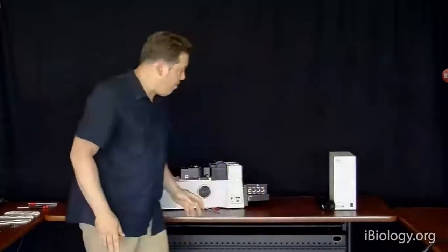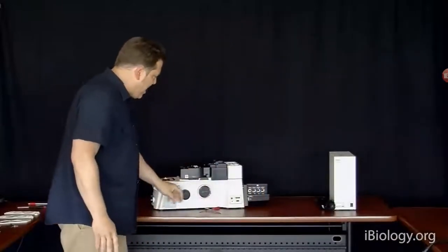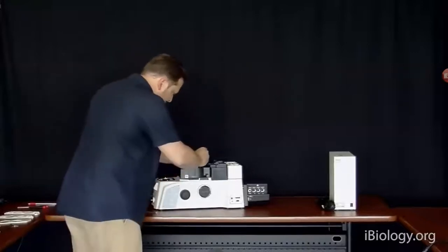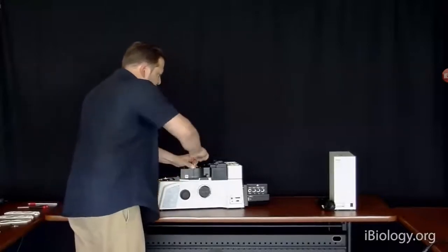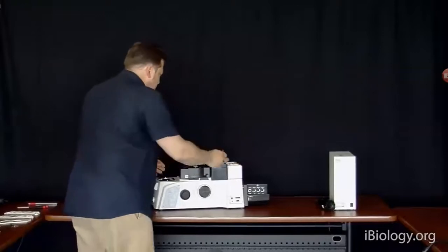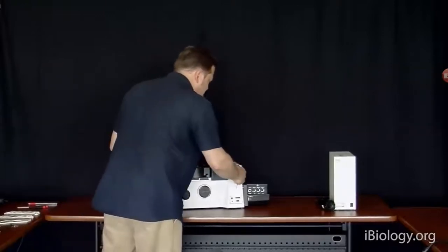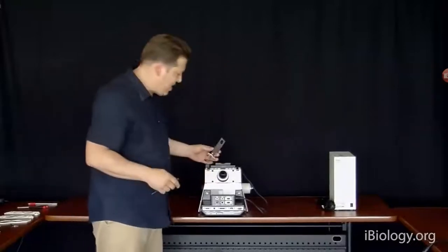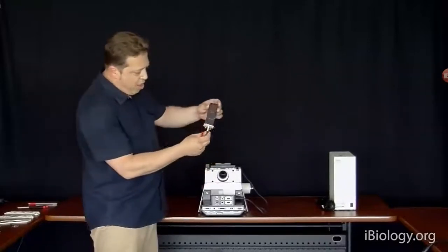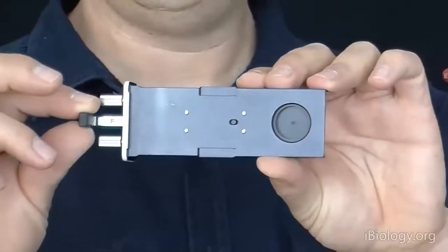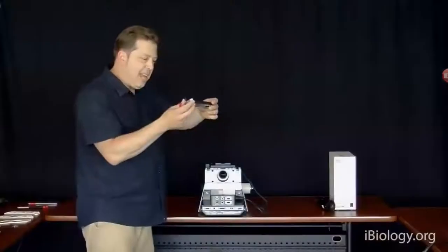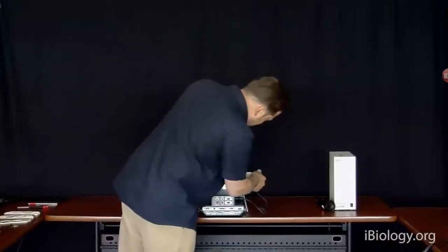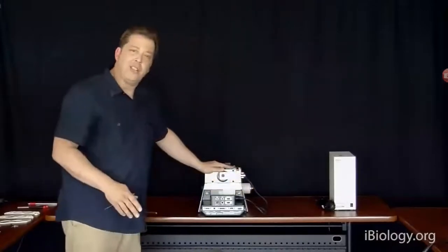Okay, so now we're really getting down to the base of the microscope. Next component we'll go through is when you have that epi light that comes into the microscope, there's actually a field aperture. I'm going to turn the microscope around the back so that you can really take advantage of this. This is what we call the field iris, and that iris opens and closes and sits in the microscope in this position with the illuminator in place.